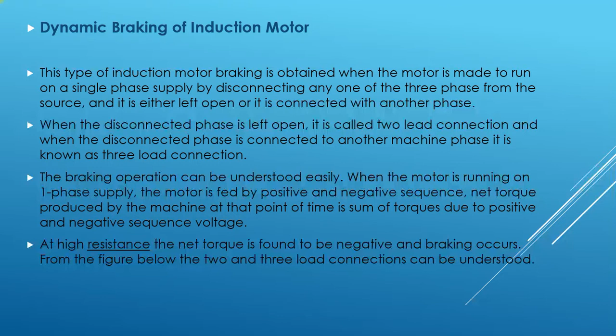So from the figure you should know that this is the normal running condition of the motor. If I disconnect any one of the supply and it is kept open, that means only two leads are connected, and we connect some external resistance to dissipate the stored energy in the machine. This type of connection is called two-lead connection. Suppose this disconnected phase is connected to any one of the phases, then it is called three-lead connection.